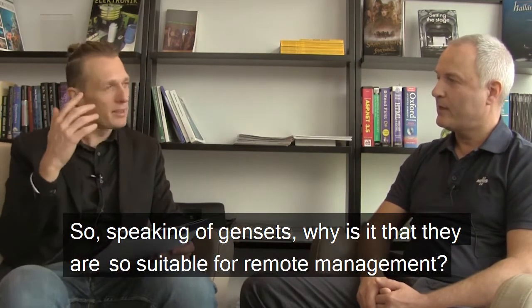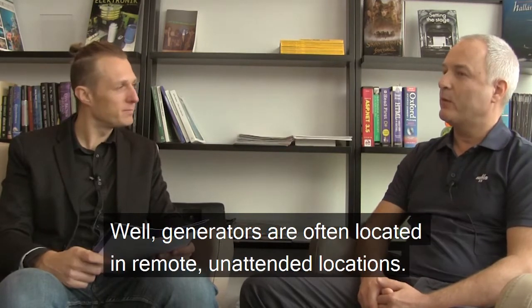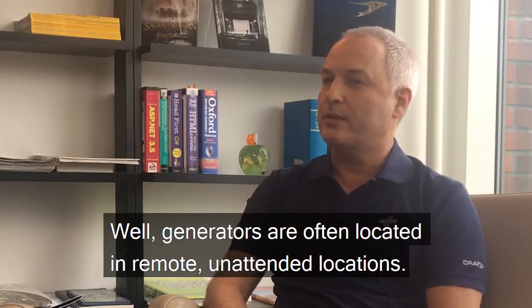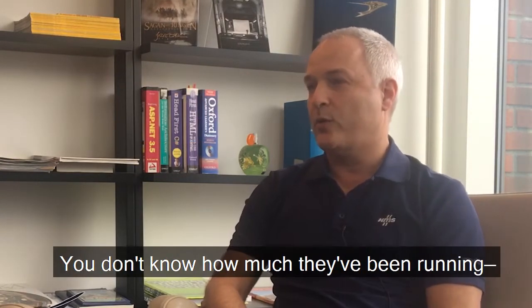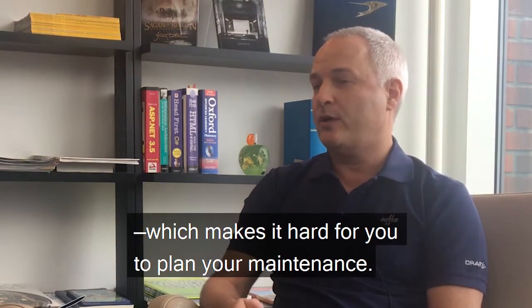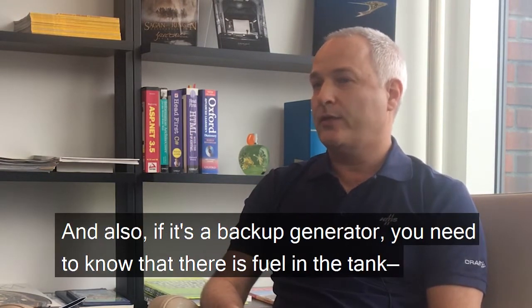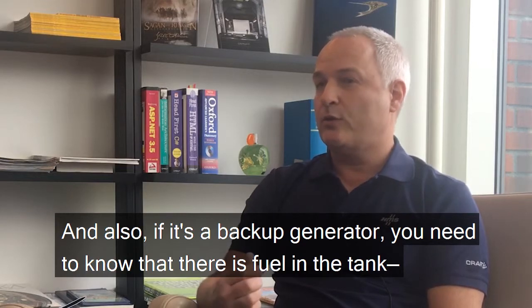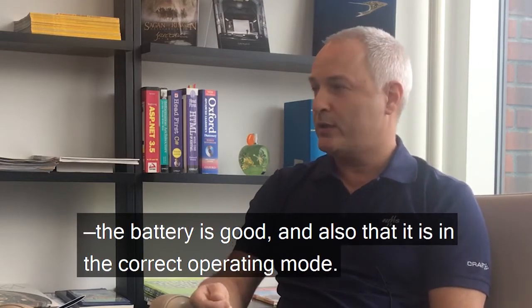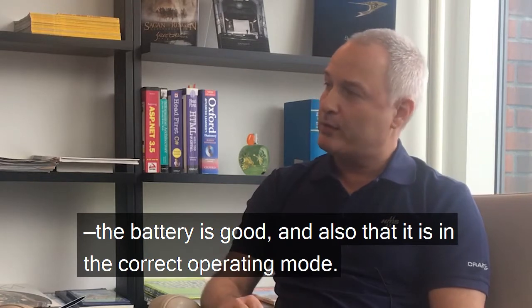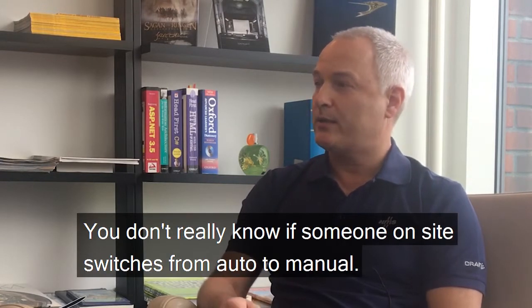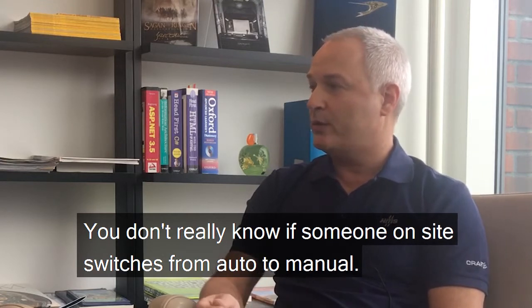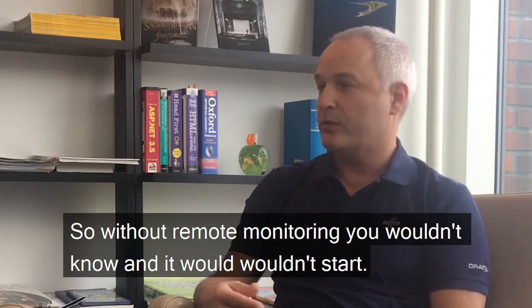Thanks, Thomas. So speaking of gensets, why is it that they are so suitable for remote management? Well, generators are often located in remote, unattended locations, so you don't really know much about them. You don't know how much they've been running, which makes it hard to plan maintenance. And if it's a backup generator, you need to know there's fuel in the tank, the battery is good, and that it's in the correct operating mode. You don't really know if someone on site switches from auto to manual or even just pressed an emergency stop. So without remote monitoring, you wouldn't know, and it wouldn't start.